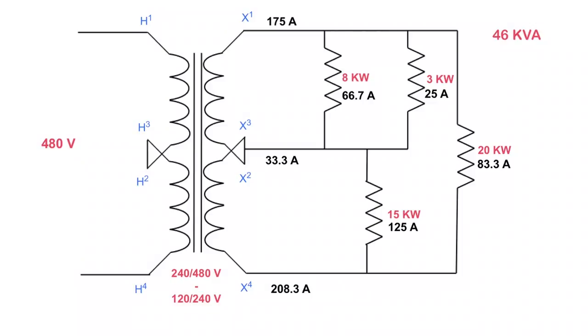Now some of you might be thinking: with transformers, power in equals power out, so why can't we just add up all our powers — which is 46 KVA in this case — and say the minimum KVA is 46 KVA? Well, if we take that 46 KVA, we have to split it equally across each winding, giving us 23 KVA on each winding. Let's determine what current those windings would be rated for: 23,000 divided by 120 gives me 192 amps on each side.